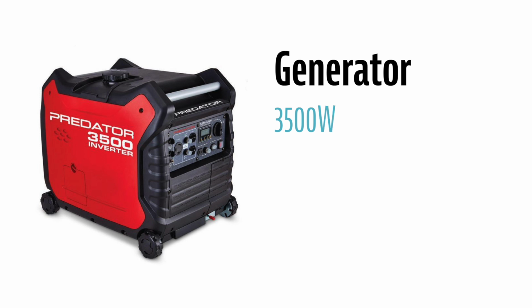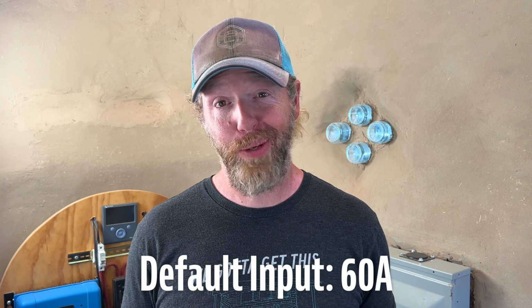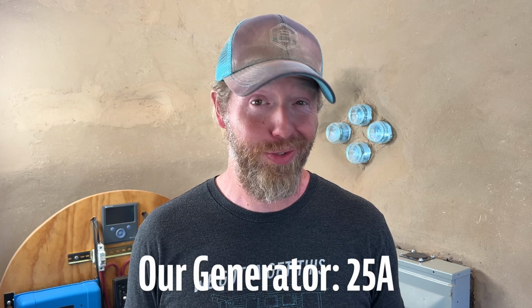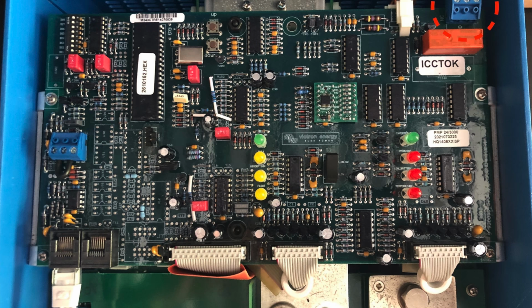We have a small 3500 watt Harbor Freight generator, but Victron is assuming we'll be using something much larger as a backup. The default input current limit is upwards of 60 amps, but our generator only puts out about 25. You're going to have to change this setting for smaller generators, but Victron does not make this easy. We had to do the dip switch dance, a very convoluted way to set your input current via tiny switches behind the top panel of the Quattro.